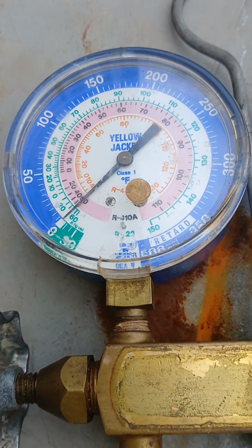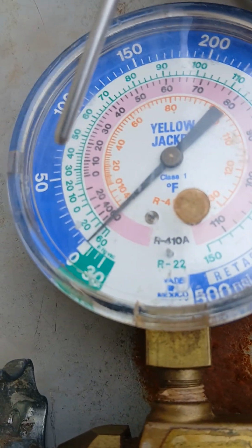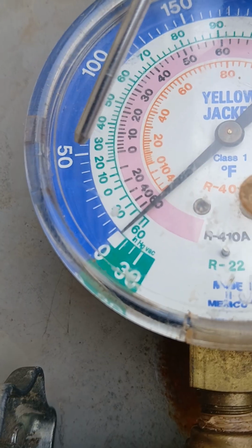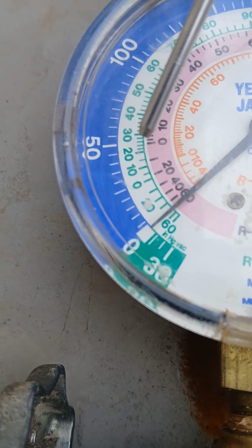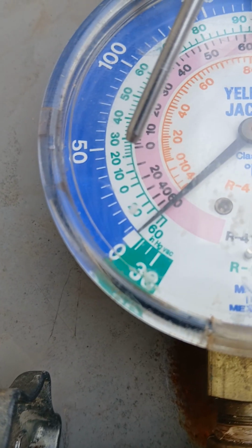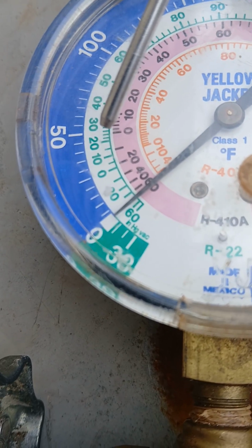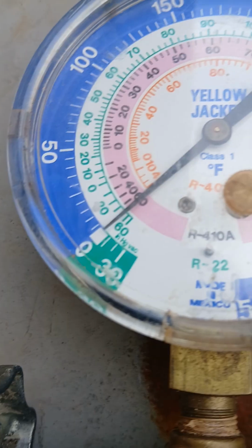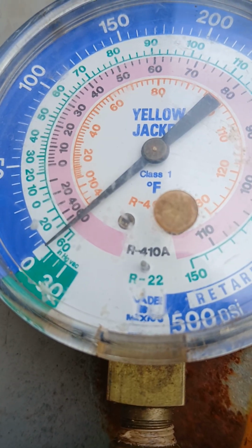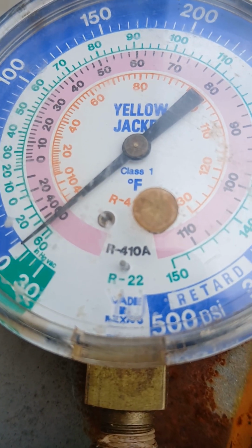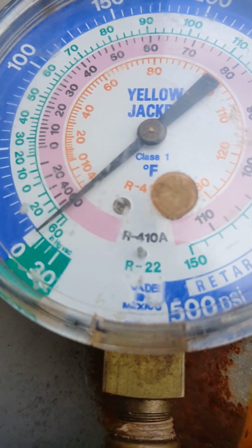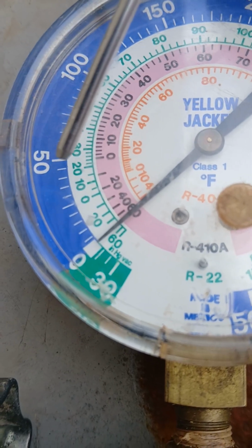Say for instance one hooked the gauges up, and the pressure's low, just above the 50 mark. We cross-reference that, and if we're using R22, we come to 30 degrees. So if we have 32 degrees as freezing, we're below freezing. Hence the A coil may begin to freeze, and once it freezes, it's kind of a self-fulfilling prophecy, so to speak: it freezes and creates ice, so it has more difficulty allowing airflow across or through the coils, and then it begins to accumulate more ice.